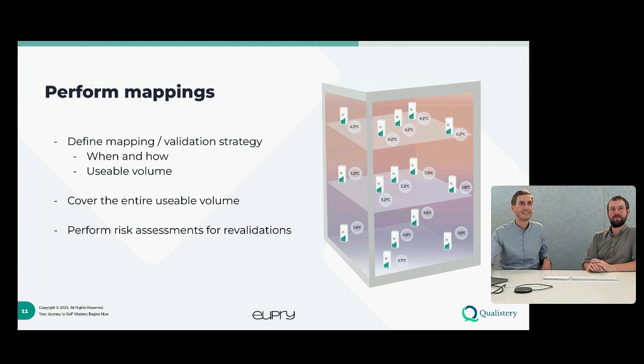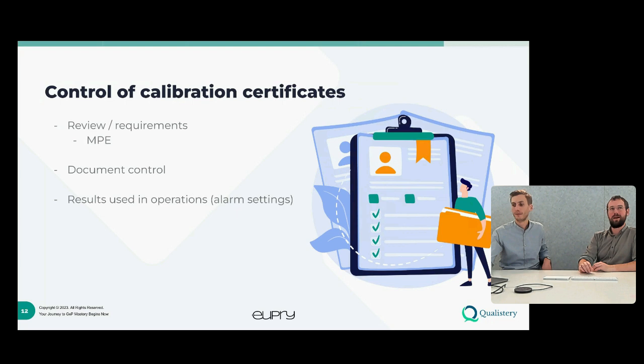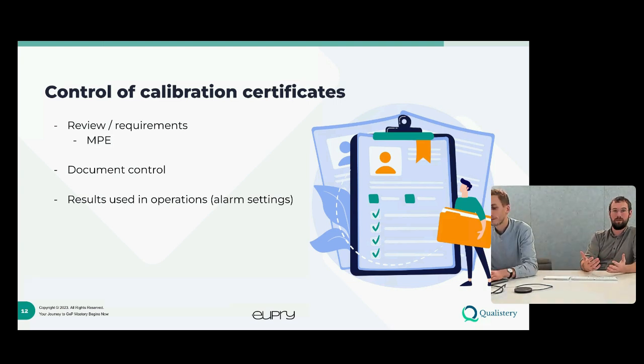Moving on here. Yes, great. So one of the other parts is really to control the calibration certificates, and not only the calibration certificates, but the calibration process. One of the things that tends to catch an auditor's focus is whether you've done review on your calibration certificates.